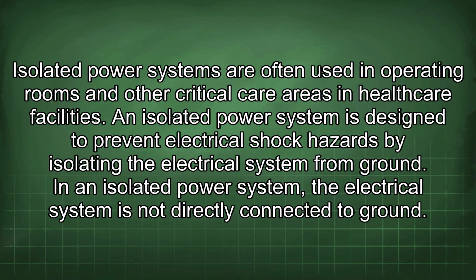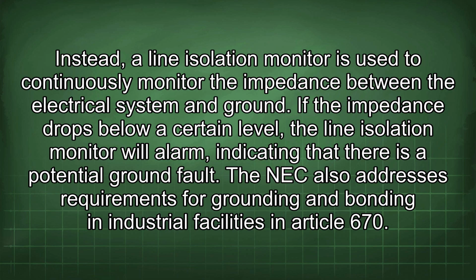Isolated power systems are often used in operating rooms and other critical care areas in healthcare facilities. An isolated power system is designed to prevent electrical shock hazards by isolating the electrical system from ground. In an isolated power system, the electrical system is not directly connected to ground. Instead, a line isolation monitor is used to continuously monitor the impedance between the electrical system and ground. If the impedance drops below a certain level, the line isolation monitor will alarm, indicating that there is a potential ground fault.